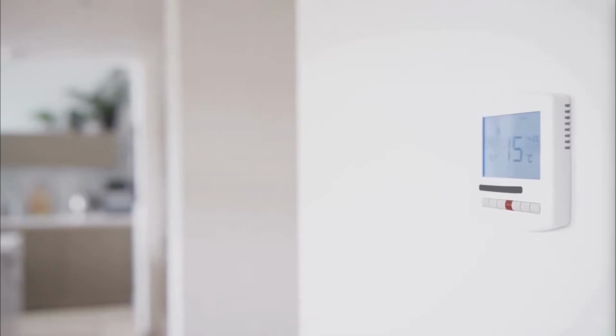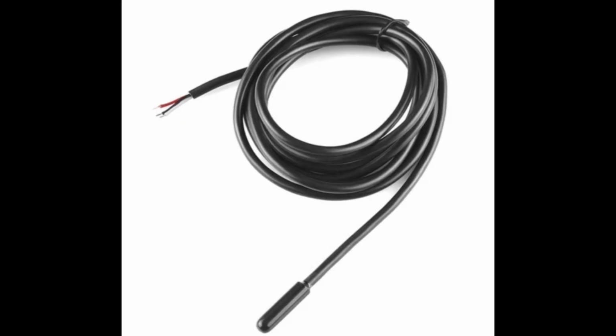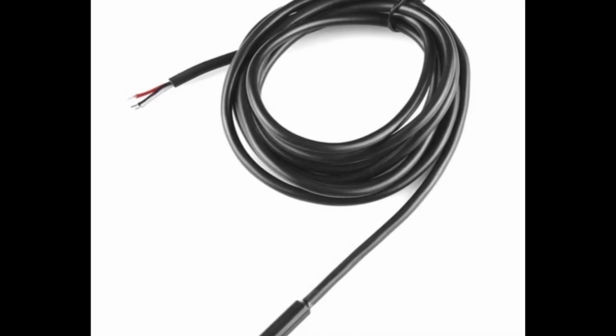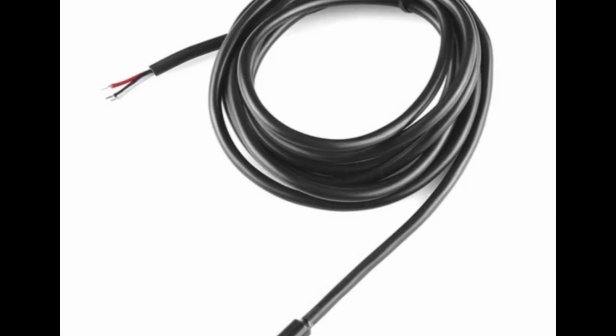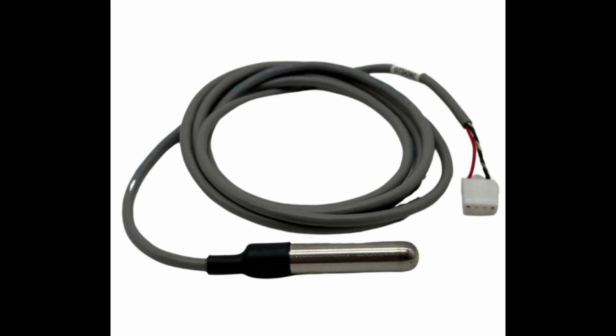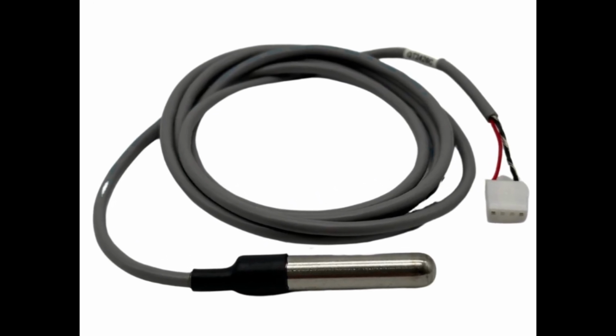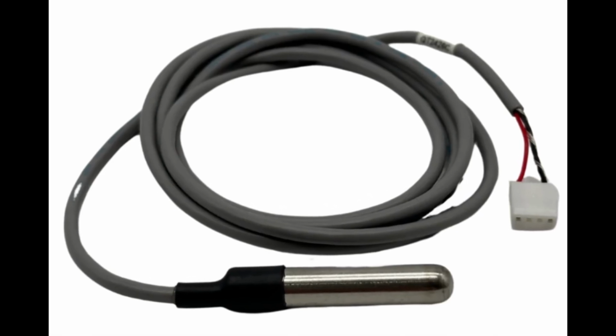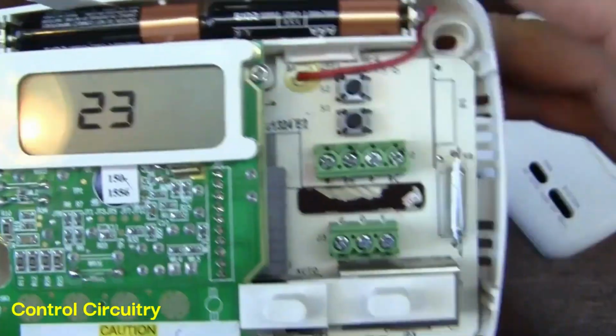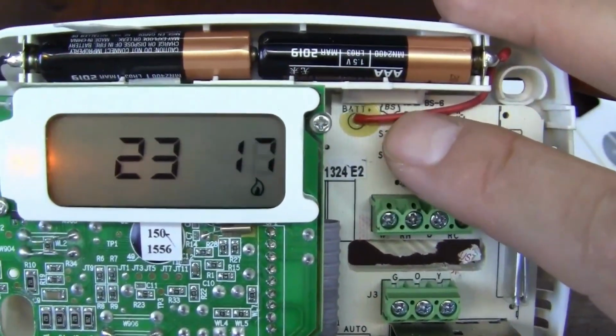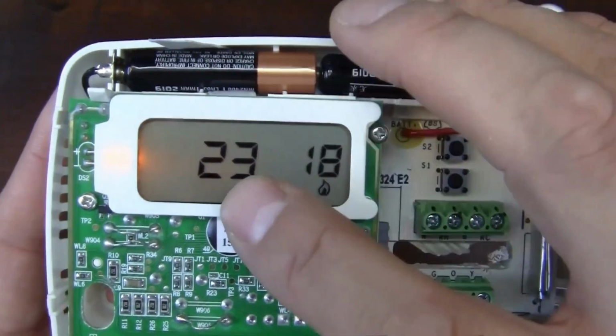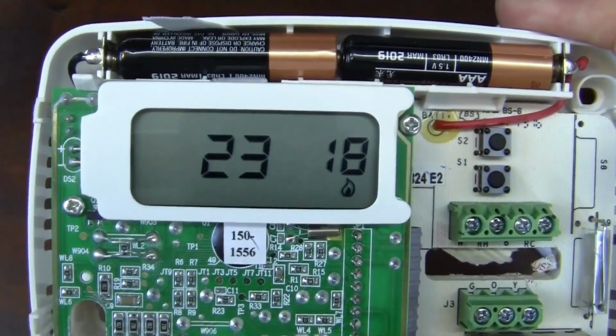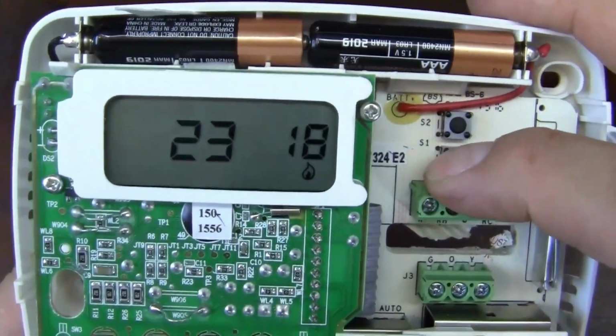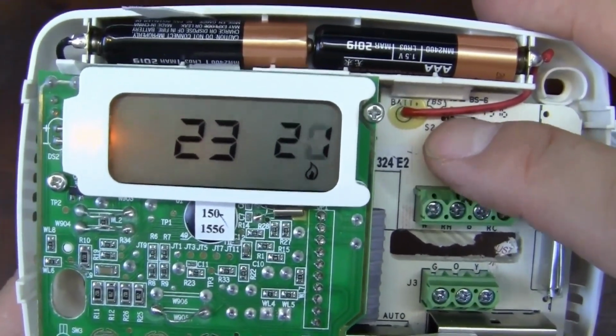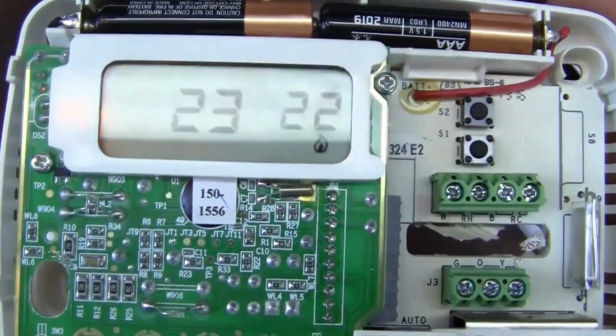At first glance, a thermostat looks simple. But inside, it's a carefully balanced system where every part has a job. Let's break it down. 1. Temperature sensor. This is the thermostat's sense of touch. It constantly measures the temperature of the surrounding air using thermistors, digital temperature sensors, or older mechanical elements in legacy systems. If this sensor is inaccurate, everything downstream is wrong. The thermostat doesn't know it's wrong, it just makes bad decisions confidently. 2. Control circuitry, the brain. This is where thinking happens. The control board compares actual temperature to the set point. It applies logic rules, on-off thresholds, delays, schedules. It also prevents rapid cycling that can damage HVAC equipment. In smart thermostats, this is also where learning algorithms run, occupancy patterns are analyzed, and weather data is factored in.